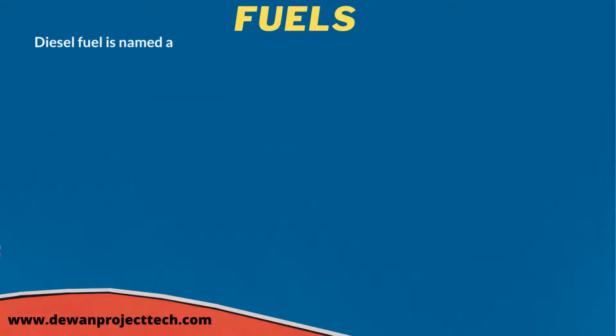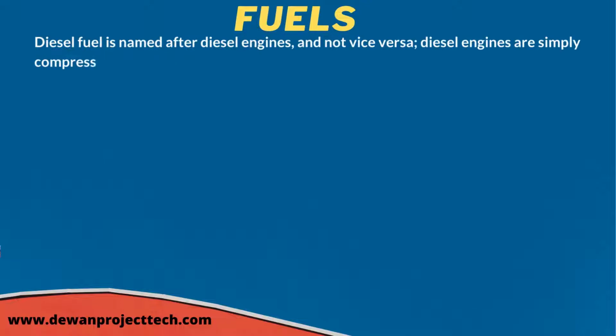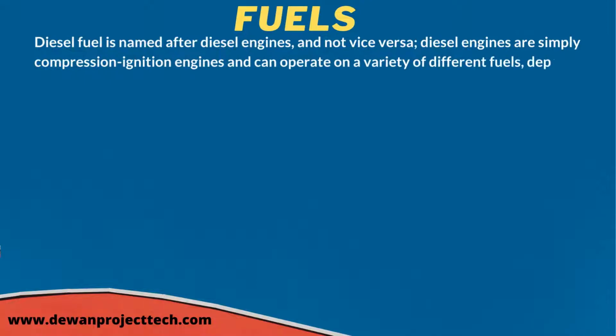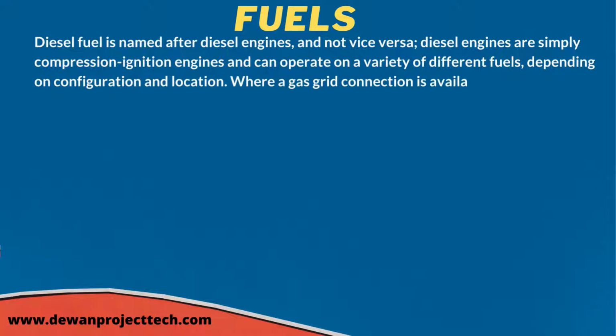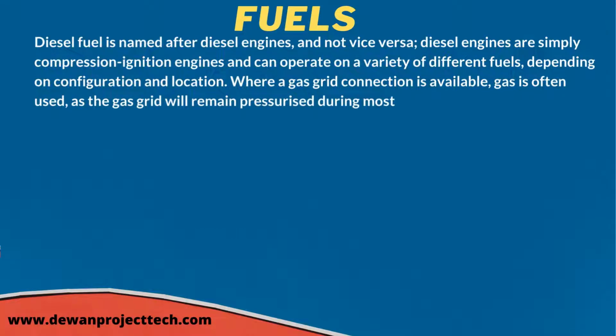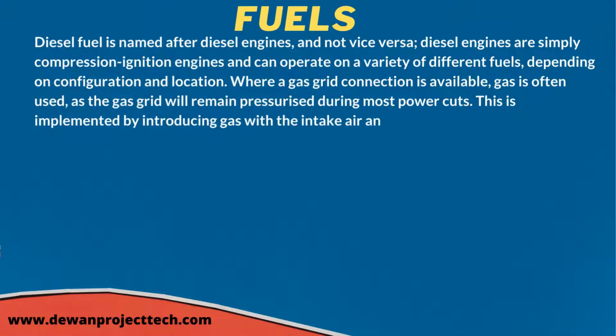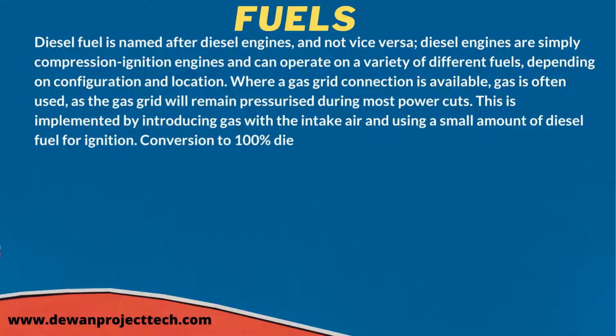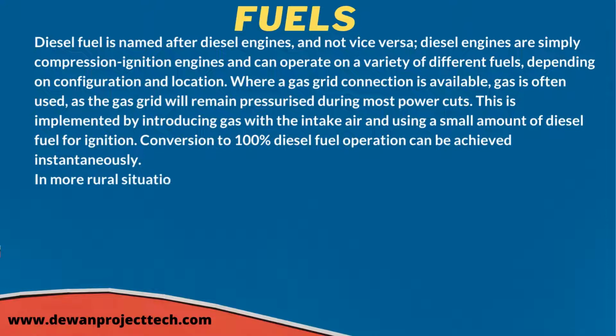Fuels: diesel fuel is named after diesel engines, and not vice versa. Diesel engines are simply compression ignition engines and can operate on a variety of different fuels, depending on configuration and location. Where a gas grid connection is available, gas is often used, as the gas grid will remain pressurized during most power cuts. This is implemented by introducing gas with the intake air and using a small amount of diesel fuel for ignition. Conversion to 100% diesel fuel operation can be achieved instantaneously in more rural situations, or for low load factor plants.